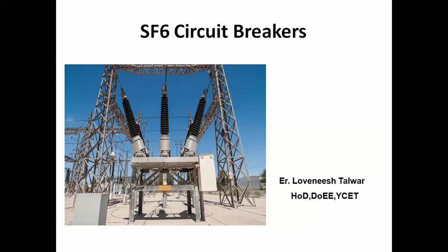So the only thing you have to keep in mind is that whenever the circuit breaker has to be operated under faulty conditions, you have to isolate the faulty system. And when you have to isolate the faulty system, the circuit breaker has to be operated. But when the circuit breaker operates due to high potential, high currents or voltages, an arc is struck between the moving contact and the fixed contact, and you have to quench this arc in the minimum possible shortest time.